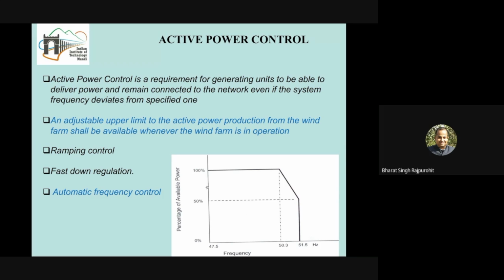In some cases, the output can be controlled by a blade pitching mechanism. By changing the angle of the blade on which the air is striking, once again the power can be controlled. But the power grid operators, the transmission system operators, are not bothered about how the technology is changing the power. They are more concerned that they want to control the active power output from a wind turbine. So this is how the control is exercised for a variable speed system or a fixed speed system.